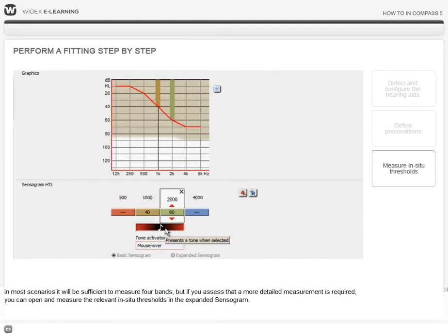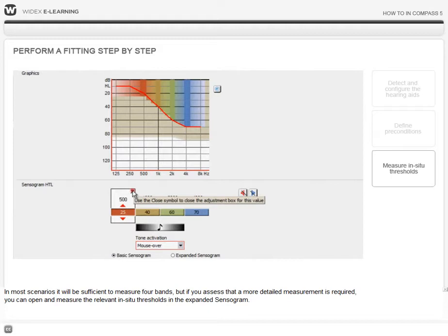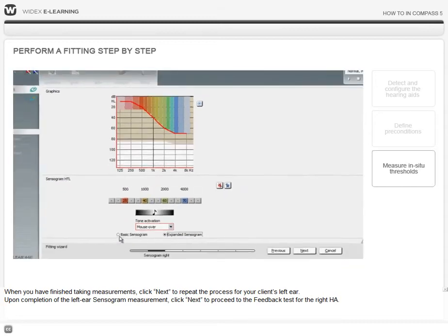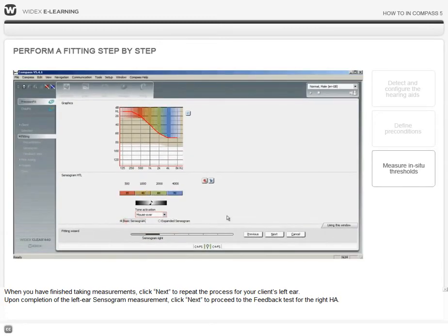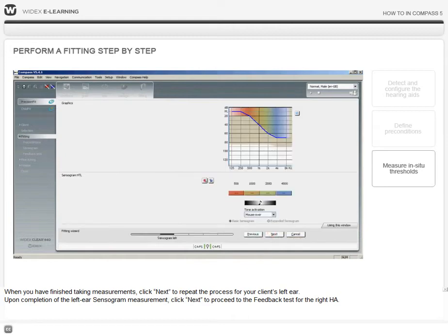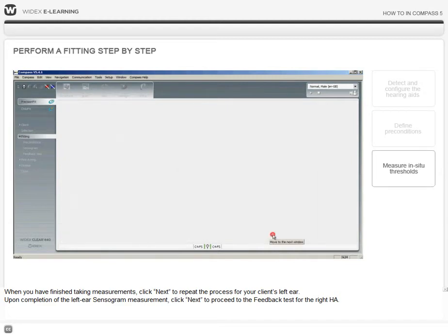In most scenarios, it will be sufficient to measure 4 bands, but if you assess that a more detailed measurement is required, you can open and measure the relevant in situ thresholds in the expanded Sensogram. When you have finished taking measurements, click Next to repeat the process for your client's left ear.